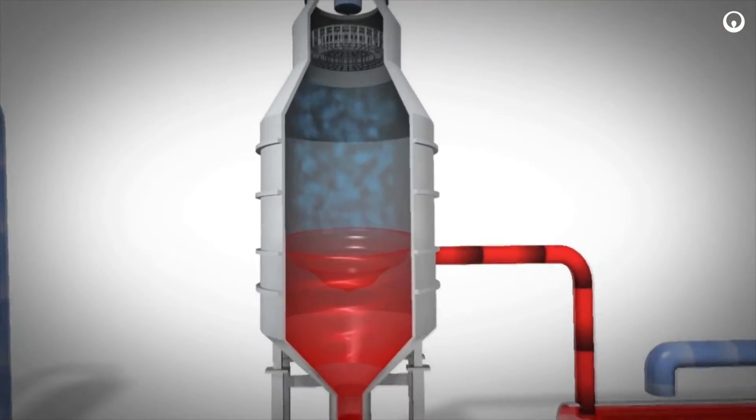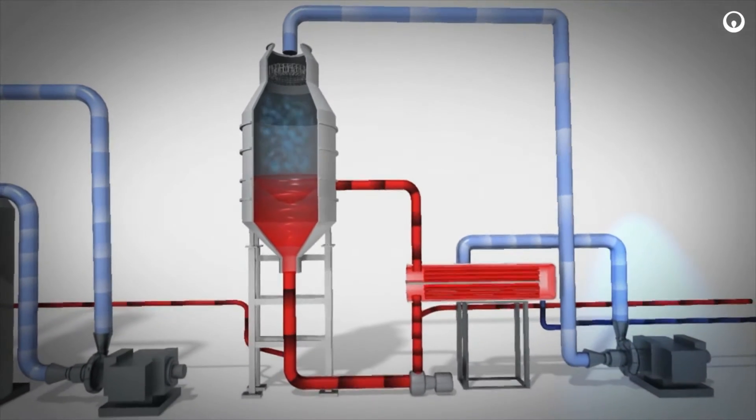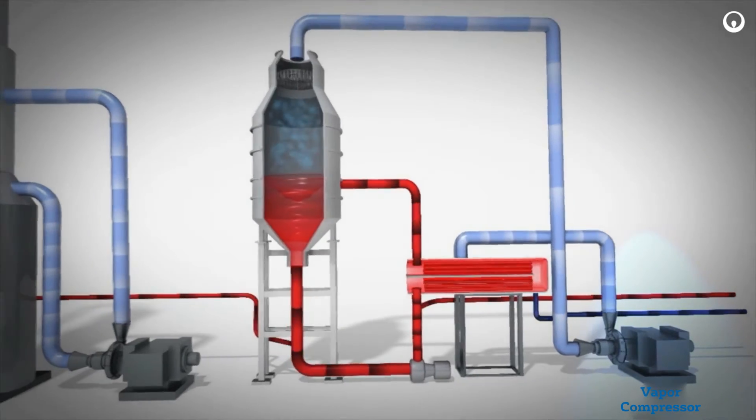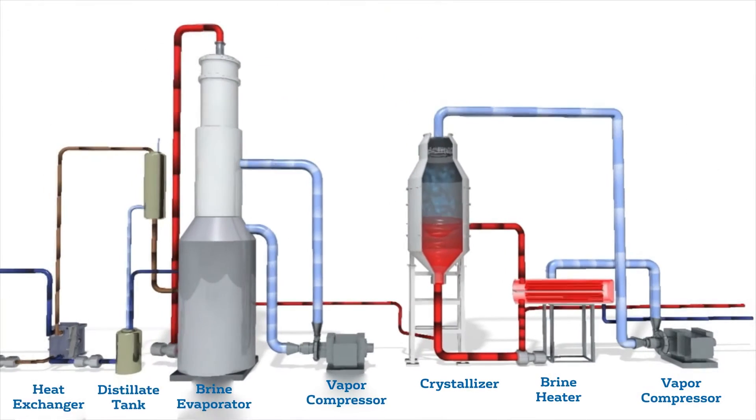The flashed vapor in the vapor body flows through the mist eliminator to the vapor compressor. Vapor from the compressor is routed to the shell side of the shell and tube heater where it condenses and is recovered as condensate. Recovered distillate is available for recycle and reuse.